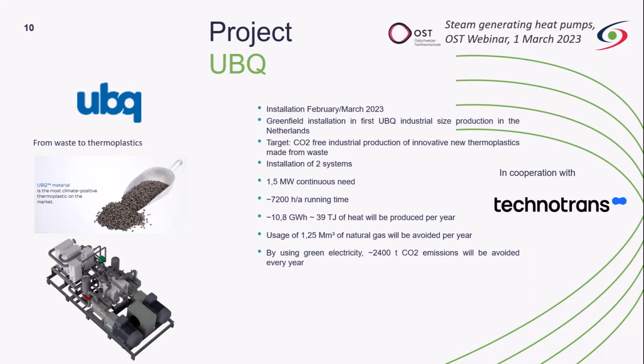The entire high temperature heat demand of UBQ is 1.5 megawatts. We have a runtime of 7,200 hours at this site, means we will generate 10.8 gigawatt hours of heat per year. So it means we can avoid 1.25 million cubic meter of natural gas. By using green electricity, which is the aim from UBQ, we have a CO2 avoidance of 2,400 tons per year.